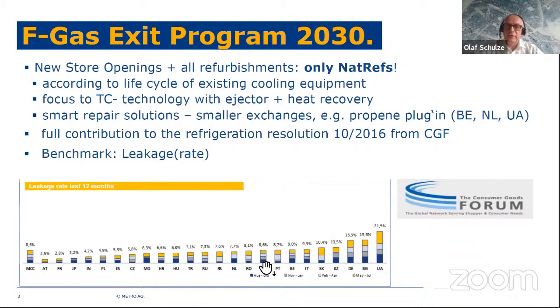Dear all, we have created an F-gas exit program. It was created in '13 in the end. We like to install in each new store opening, wherever in this world, and in all refurbishment of existing stores, only natural refrigerants. We like to do it in accordance with the life cycle. Clear, when a store, HFC store, is end of life cycle, we like to install only natural refrigerants. You know it, NatRef means GWP lower than 150, but in practice we are using CO2 or propane.